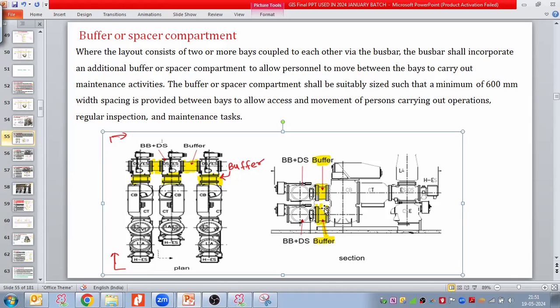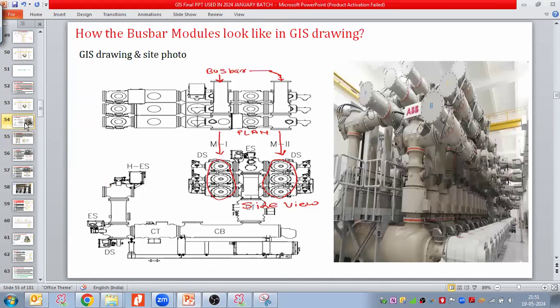Why have we given the buffer module here? When we require any kind of maintenance on the breaker, there is no need to touch the bus bar and disconnector modules. If we need to reduce the pressure, we just need to reduce the pressure of the buffer module only, 50%. My bus bar and disconnector are healthy and we have not touched them. So this buffer module provides this provision, plus it provides space so that easy access between each module and each bay can be achieved. I hope I'm clear why we take the buffer module. Am I clear?